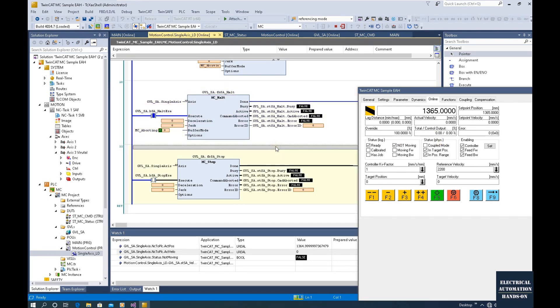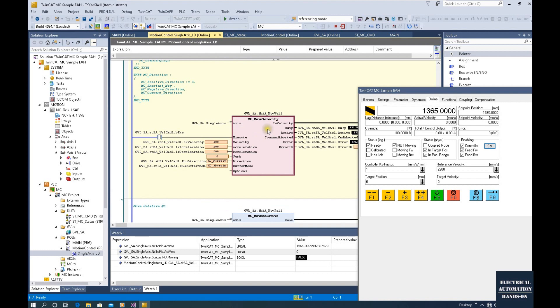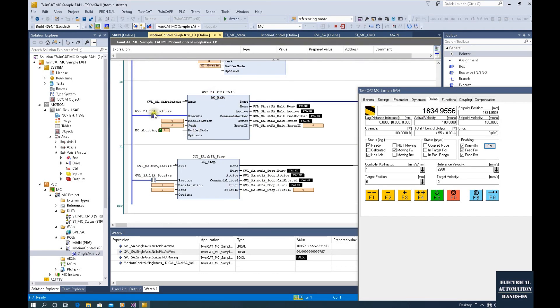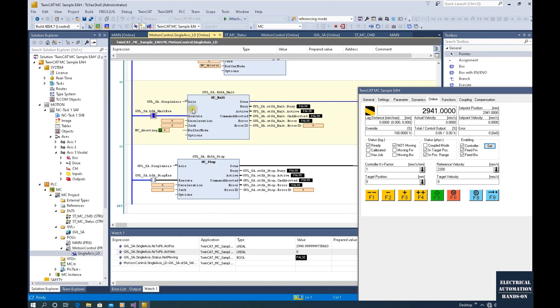After this, let's go to the velocity and trigger it. We will see the axis will start to move again, even though MC Halt is still on — because this is a rising edge only command. So turning it on again just triggers one rising edge. Now let's turn it off.